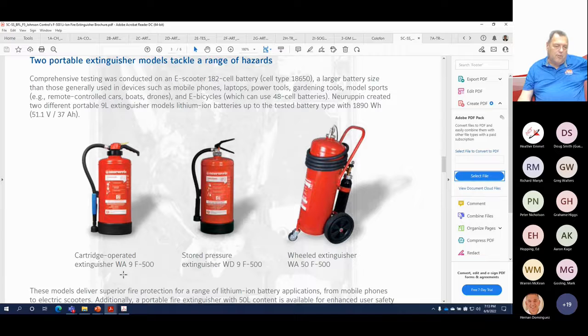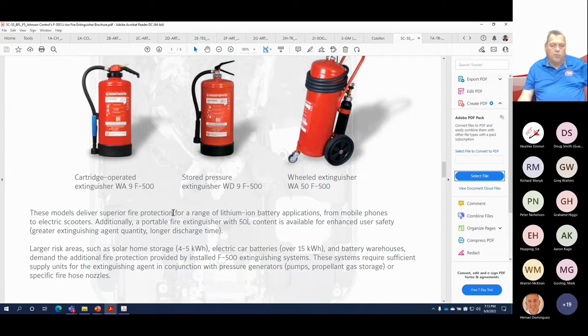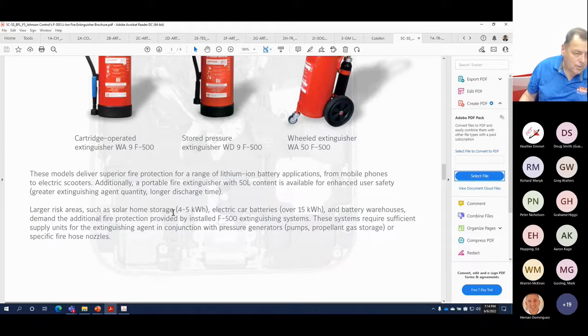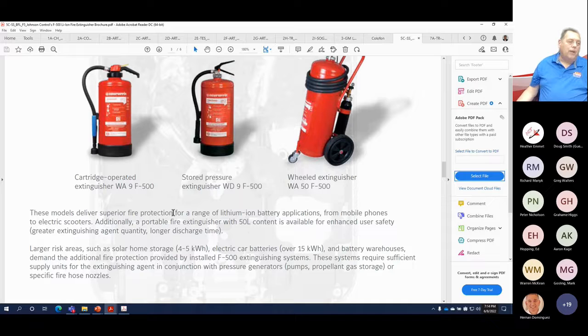We first started out with JCI doing 9-liter and 50-liter fire extinguishers. Now we have about 20 different fire extinguishers listed to the EN3 standard. They're listed to an EN3A standard because there's no L standard to list to, which is my mission: to push NFPA to an L classification for this, and then subsequent test protocols. There's a lot of confusion about what lithium-ion batteries are, so what it's classified as. It's probably an A. I'm really safe with my ABC fire extinguisher - and we just saw complete testing that invalidates that.